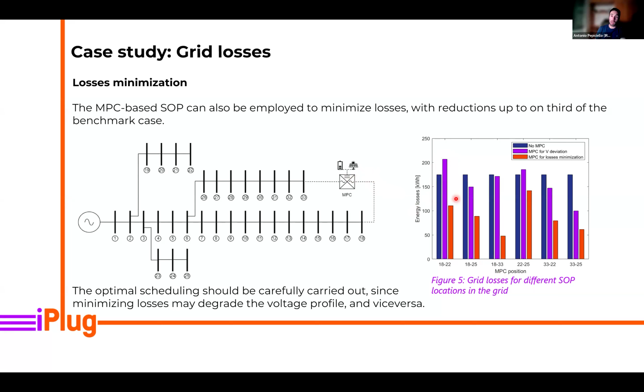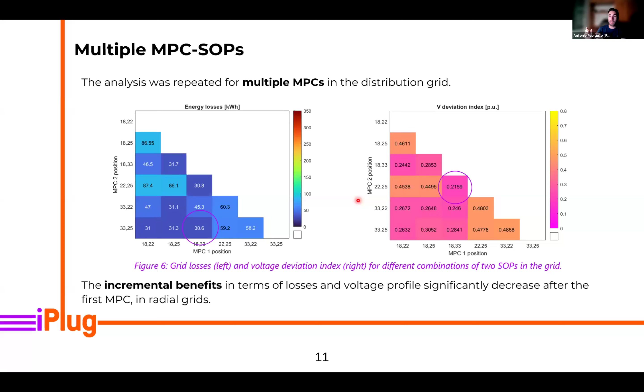We extended the analysis to more than one multiport soft open point, and at least for radial grids, we noticed that the addition of more soft open points, in addition to the first one, does not significantly increase the benefits. So the first multiport soft open point can increase a lot the benefit of the grids in terms of the voltages, losses, or other parameters. Whereas when we start adding more than one, the benefits start to be more incremental.